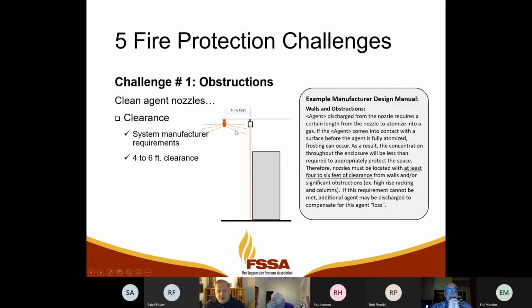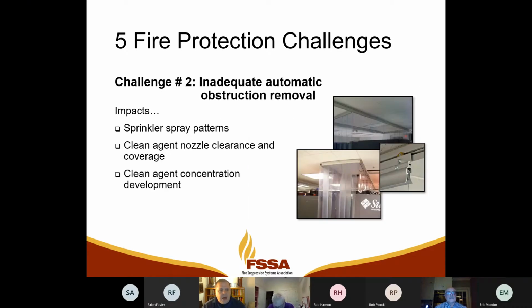If we have obstructions too close to the nozzle, what we risk is something called frosting or splashing, depending on which company is talking about it. They're talking about the same thing, but basically some of that liquid agent hits that vertical surface and then stays in its liquid phase for longer than it would if it was just flying through the air with that clearance. So in a data center where this was not accommodated or anticipated, you put in a new containment system and we can have splashing issues with our clean agent nozzles.